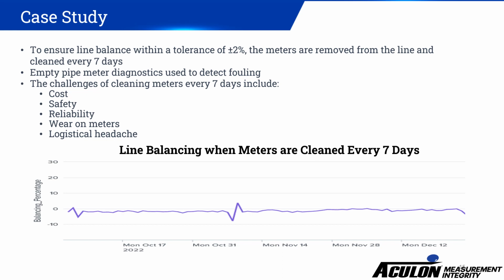When we were trying to maintain this balance on a 7-day interval, if you look at it, we would have been pulling and cleaning these meters 9 times between October 17th and December 12th. If you extrapolate that across 11 meters over a year, the likelihood of doing damage to these meters, as well as disrupting your producer or customer's flow and causing continual downtime and inaccuracy in your meter balancing and leak detection, causes a great headache that had to be corrected.